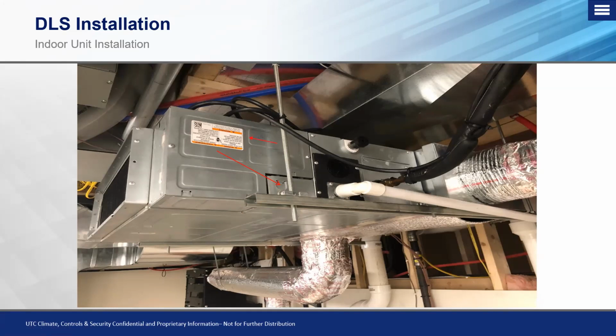Secondly, the sticker's upside down. Now, this could be something that was improperly installed from the factory on mistake, but we don't want to make that assumption. The best surefire way to tell on this is looking at where your support hangers are, but in this case, the sticker was placed properly and it's upside down, giving us an indication that, hey, this unit's installed upside down. Now, the biggest thing is you'll see these 2 drain lines on here. And with this application, this is where the mistake occurred, because they turned the unit upside down because they were trying to use this drain connection to drain out as they did.